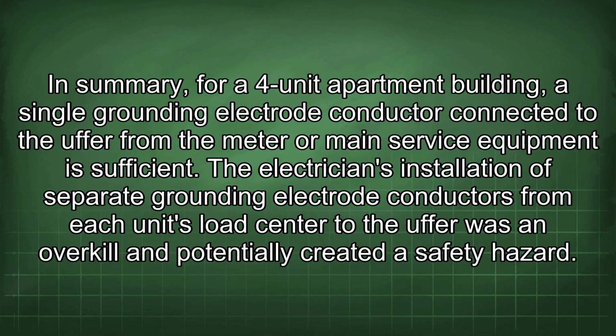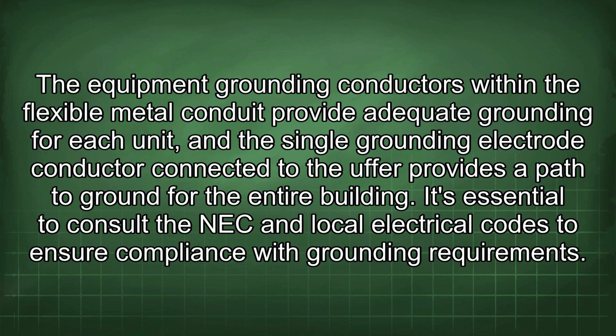In summary, for a 4-unit apartment building, a single grounding electrode conductor connected to the Ufer from the meter or main service equipment is sufficient. The electrician's installation of separate grounding electrode conductors from each unit's load center to the Ufer was overkill and potentially created a safety hazard. The equipment grounding conductors within the flexible metal conduit provide adequate grounding for each unit, and the single grounding electrode conductor connected to the Ufer provides a path to ground for the entire building.